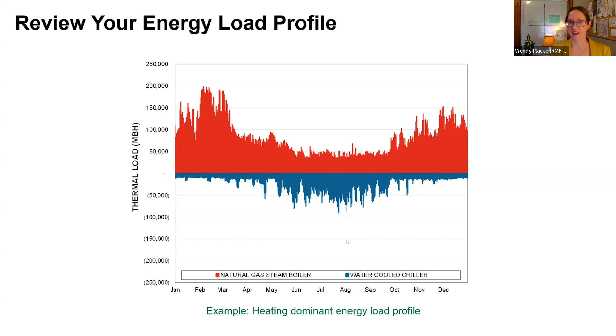How do you measure that efficiency? We use a term called the coefficient of performance, defined as the thermal energy out over the fuel or electrical energy in. I know that sounds similar to efficiency, but it's a little different because we're not just looking at combustion, where we create heat by putting in natural gas or electrical power. Instead, we might move heat from the cooling side to the heating side. In that case, we have thermal energy moved from the cooling side, say 1,000 units, and 1,000 units moved over to the heating side, but it only took 800 units of energy to do it. So now we have a COP greater than 1, which, as engineers know, you can't have with efficiency.